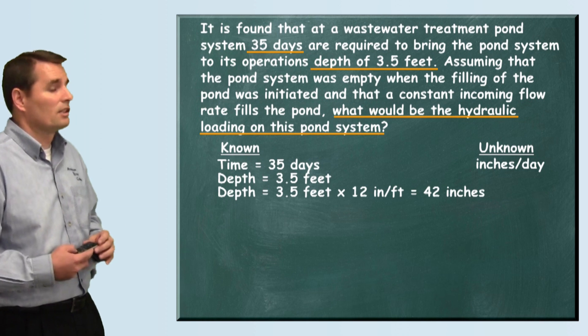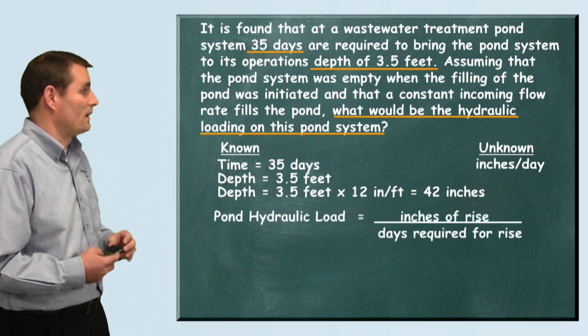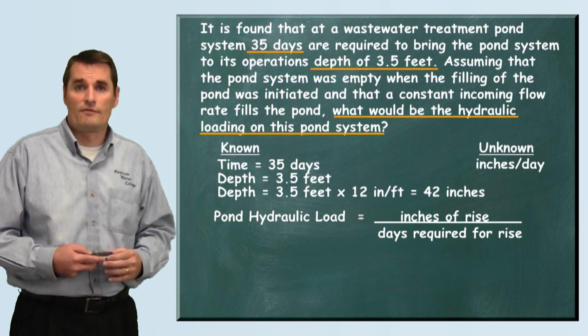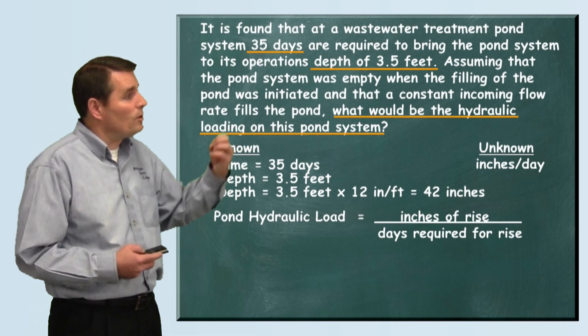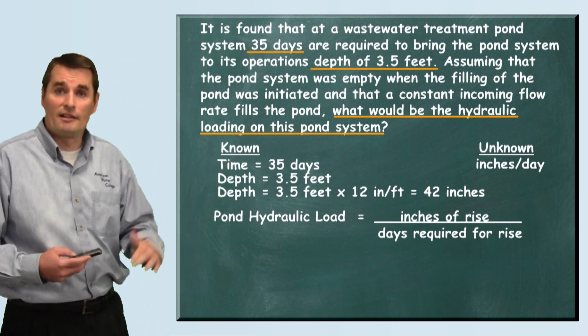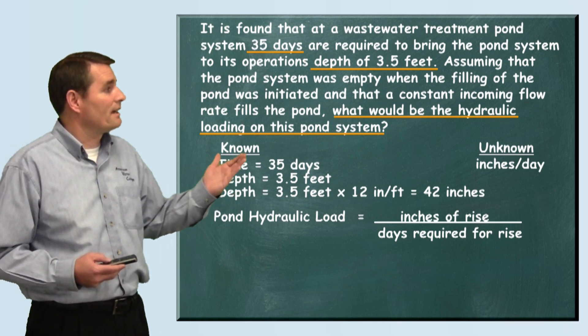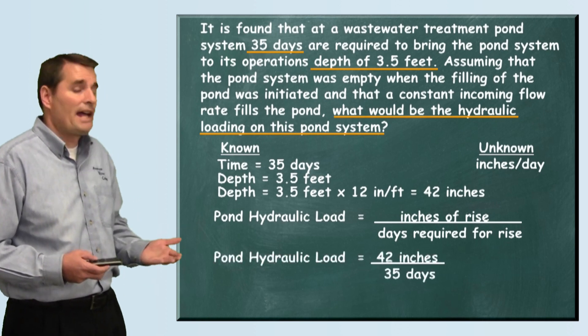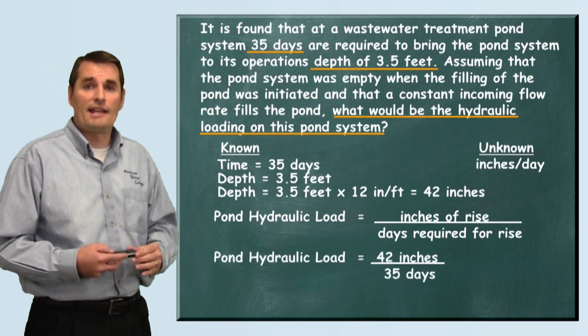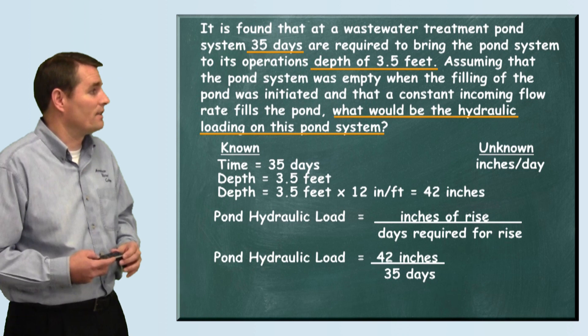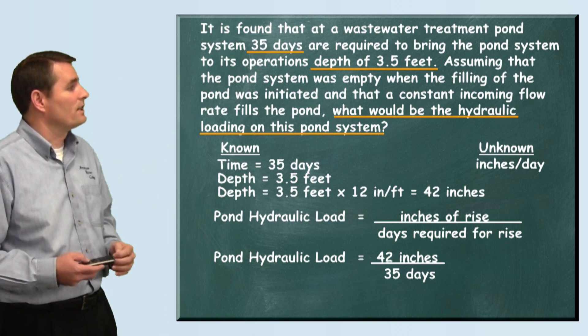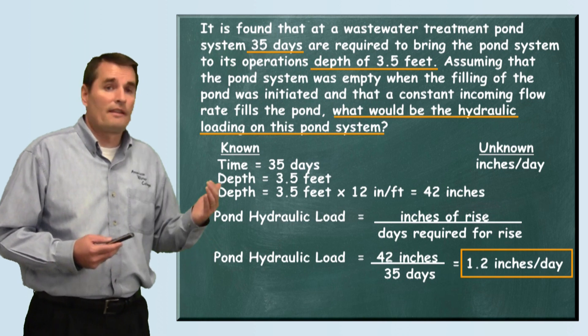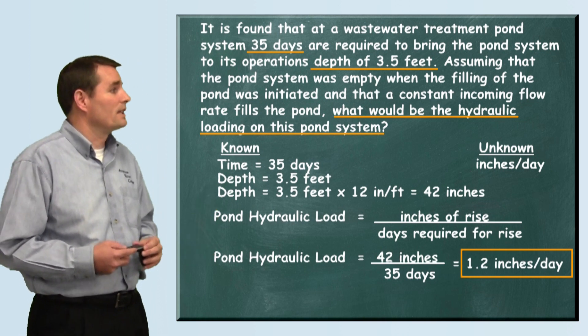The pond hydraulic loading formula is as follows: inches of rise divided by days required for the rise. Now that we've pulled all the information out and calculated our total inches in the pond, we simply take the inches of rise, which is 42, and divide it by how long it took to get that increase, 35 days. When we divide 42 inches by 35 days, we find that our answer is 1.2 inches per day.